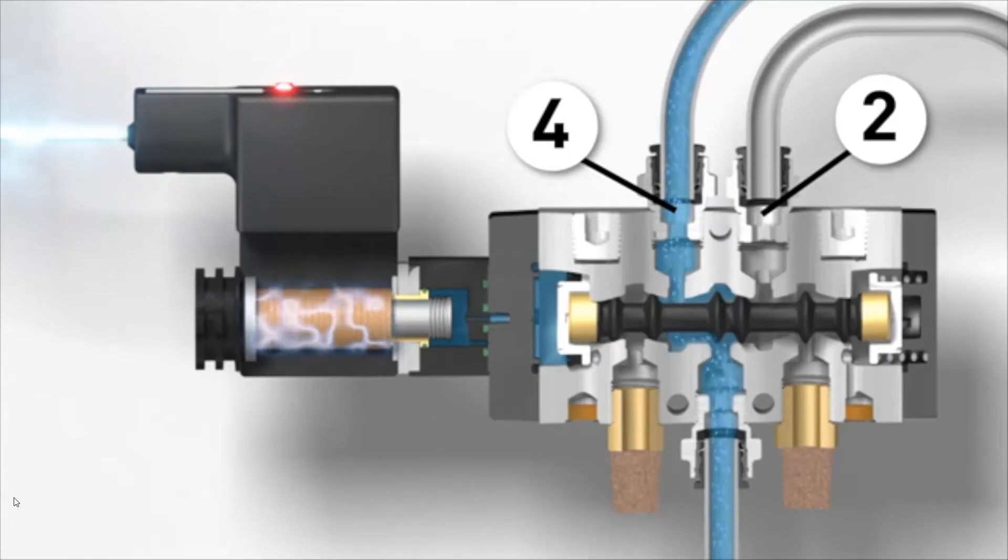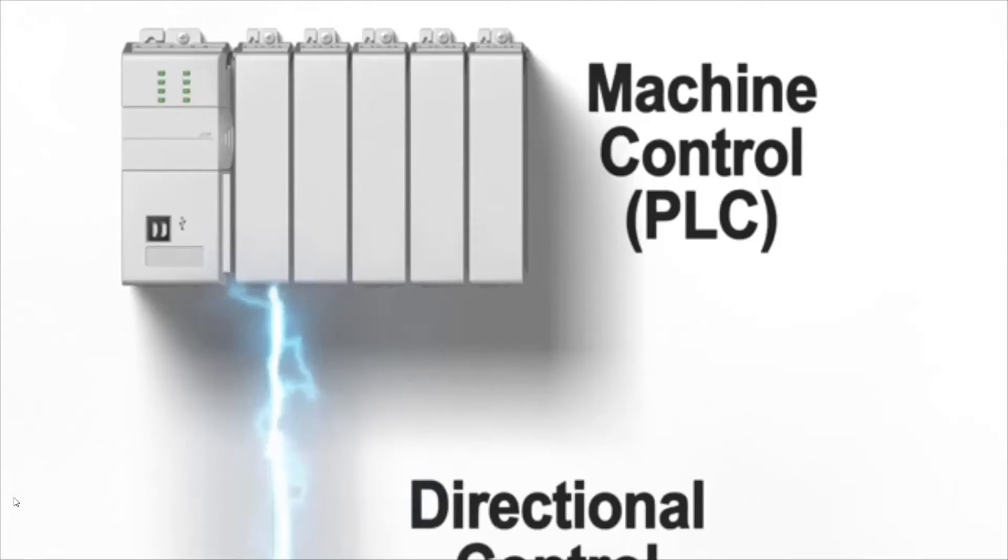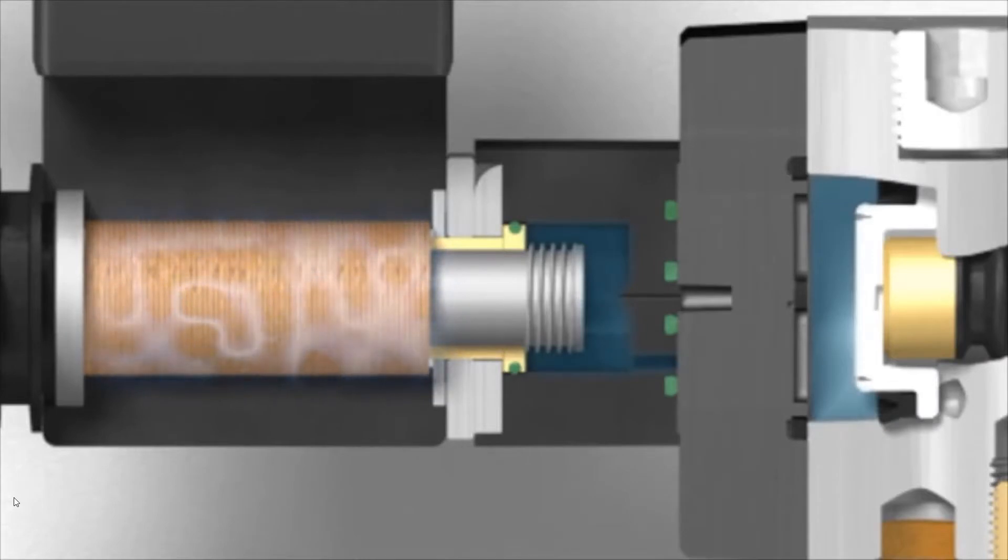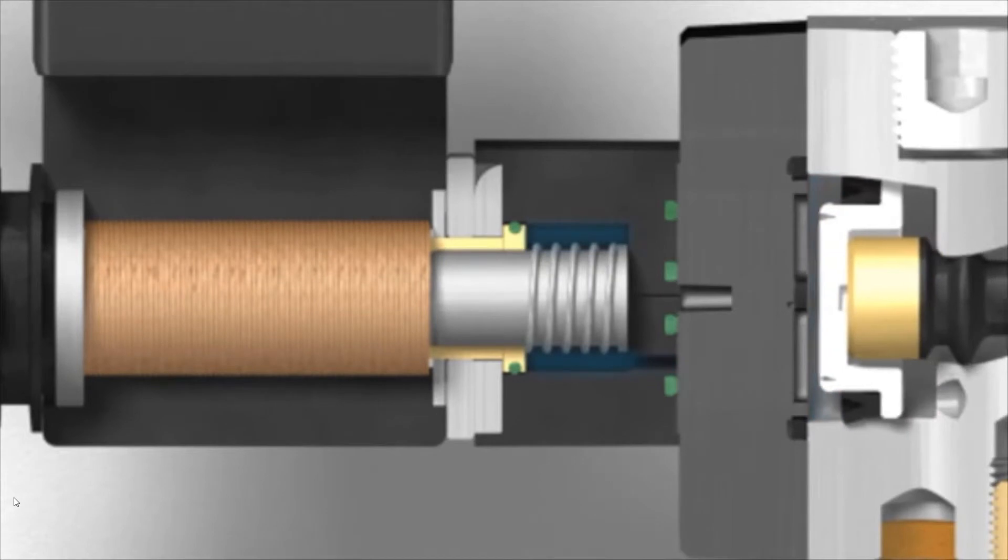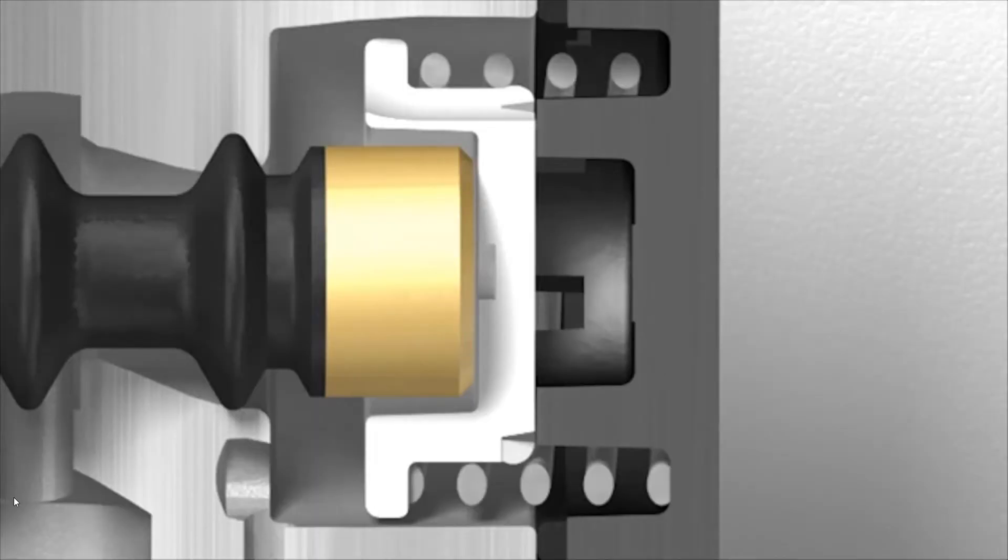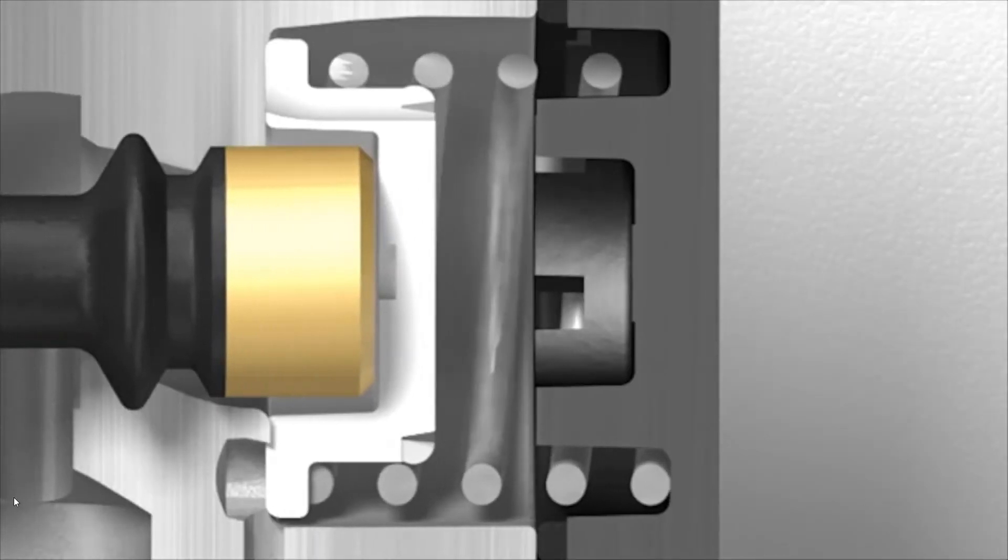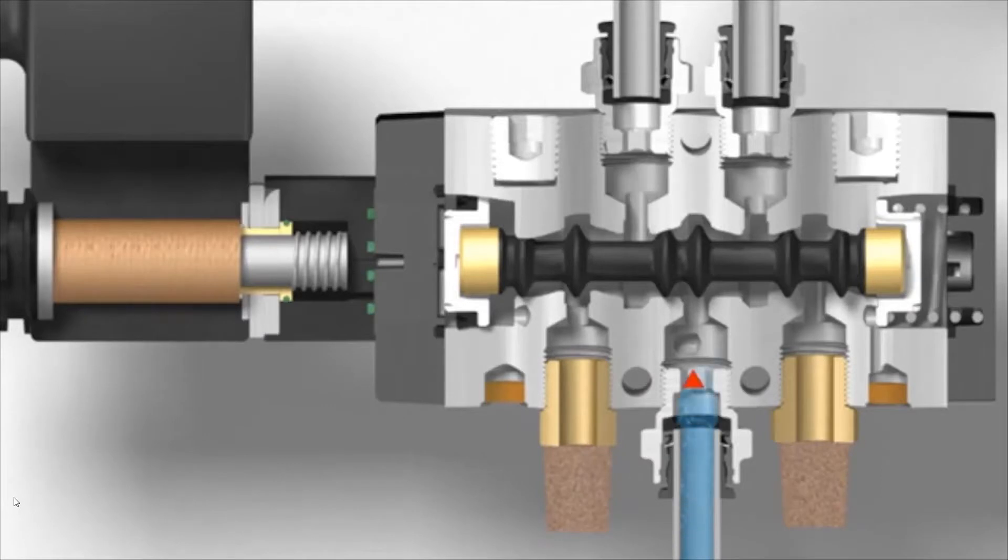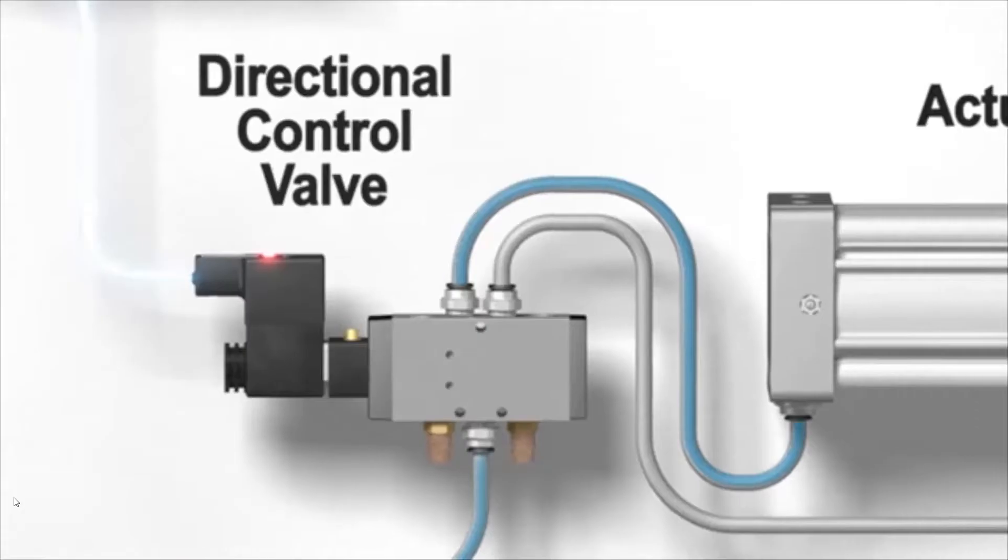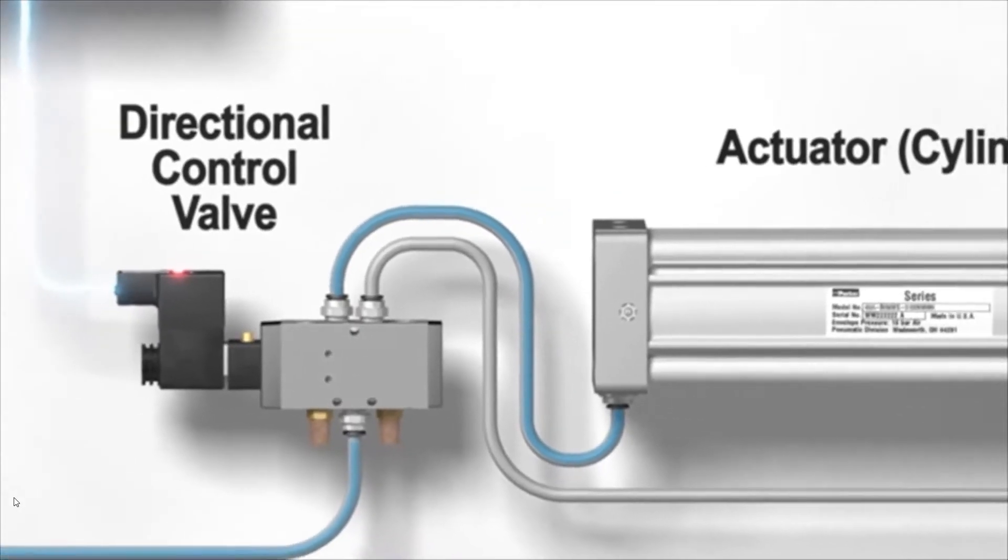When the signal from the PLC is removed, the force generated by the electromagnet is also removed, at which point the spring on the plunger returns it to its normal state, which removes the air signal that is pushing on the spool. The spring on the opposite end will return the spool to its default position once again, directing air back out the number two working port. The PLC can now direct air to whichever port is needed, whenever it is needed.